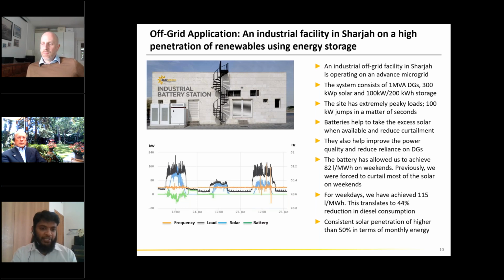It's the same load graph that I showed you earlier. You can see on the 23rd of January we had the batteries running along with the solar. This is a very small system without big generators, so the stability or frequency of the system isn't very stable because the client has machines with a peak of maybe 100 kilowatts in 1 second. They have baling machines that go on and off very frequently, and as a result the system frequency fluctuates between 49 to 51, which is quite big for a small system.